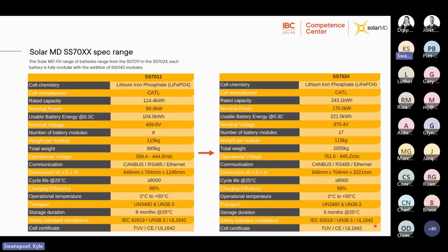So if we move over to the biggest solution, we go from 114 kilowatt hours up to 243 kilowatt hours. And then because we've gone from 8 modules to 17, our power increases from 80 kilowatt up to 170. And then the usable battery capacity, which is at 90% DoD, is 221. And the voltage has now also increased because we've gone from 8 modules in series up to 17. So we've gone from 409 volts up to 870 volts nominal. Weight per module stays the same, but because we've got more modules now, the weight of the total battery increases.